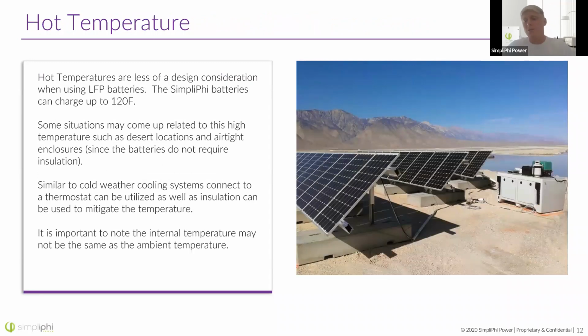Now, hot temperatures, I know we've just talked about cold temperatures for maybe 10 minutes, but hot temperatures are really not as much of a big deal. It's less often an issue. The reason is that lithium iron phosphate batteries are just so thermally stable that they can handle a high temperature even when charging. I'm talking up to 120 degrees Fahrenheit when you're charging, and even 140 degrees Fahrenheit when they're just sitting idle or discharging.